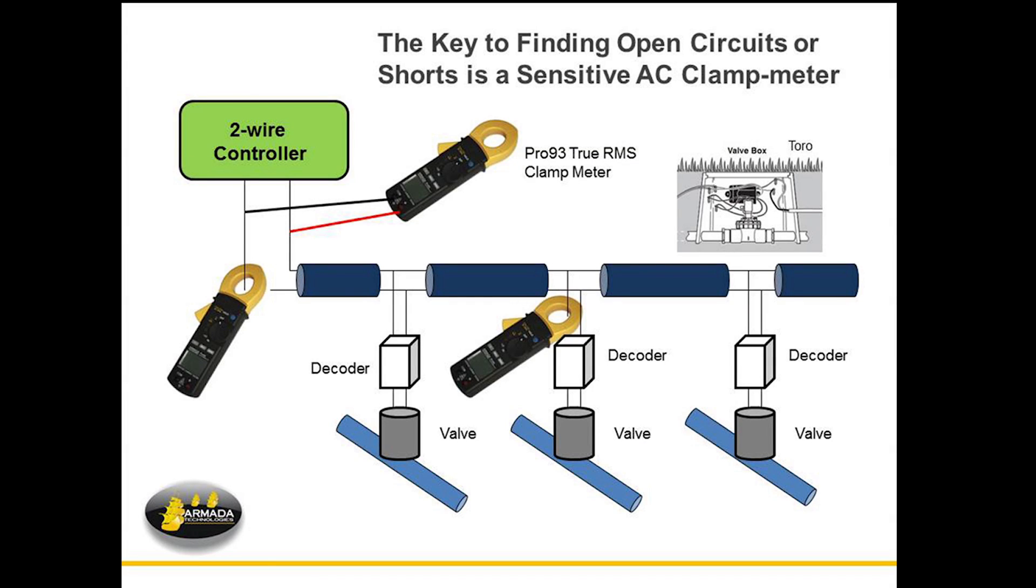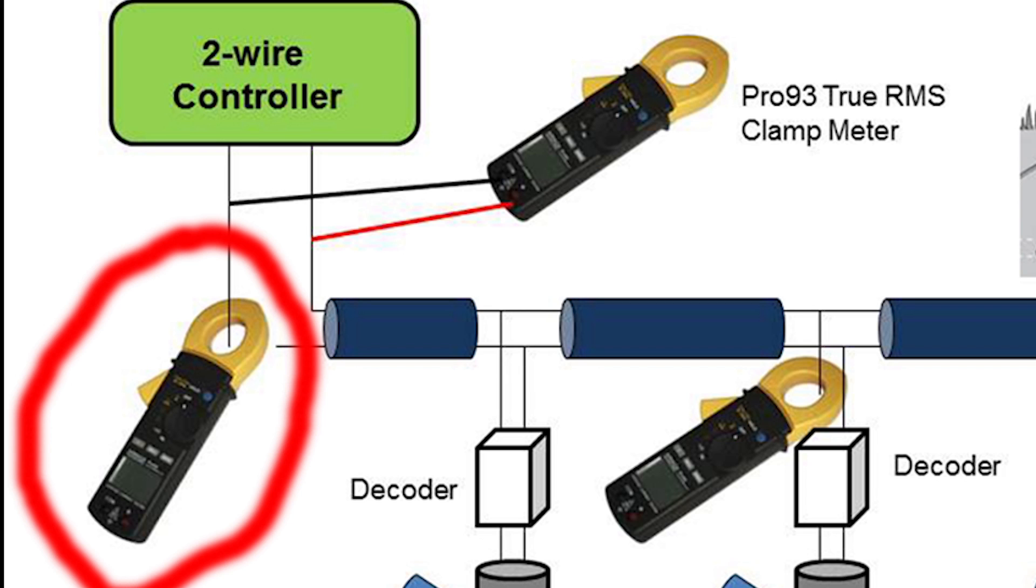This is what a typical two-wire system looks like, and this is a diagram of how you would use a Pro93 in that system to diagnose. Out of your two-wire controller comes a certain amount of milliamp current that is measurable by the Pro93. In the first instance here on the elbow, the Pro93 is going to measure—let's say there's 200 milliamps coming out of that controller.